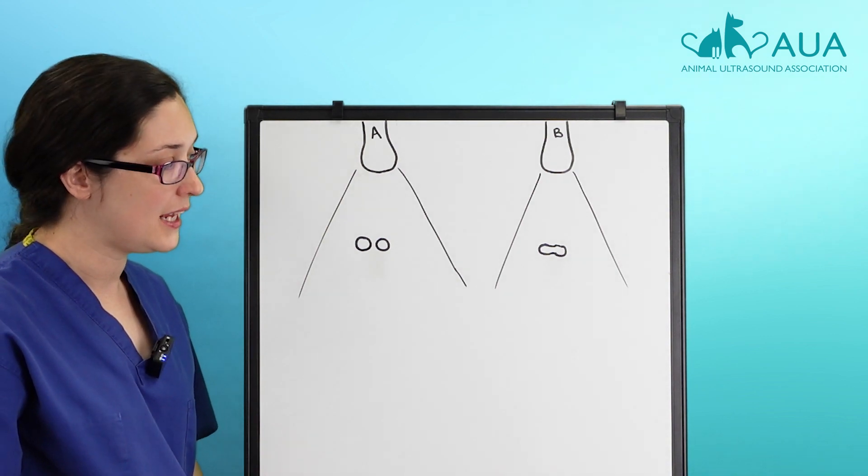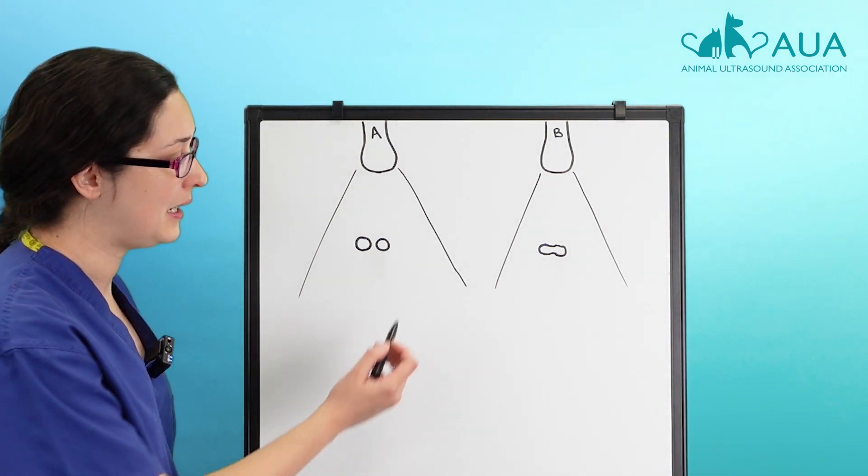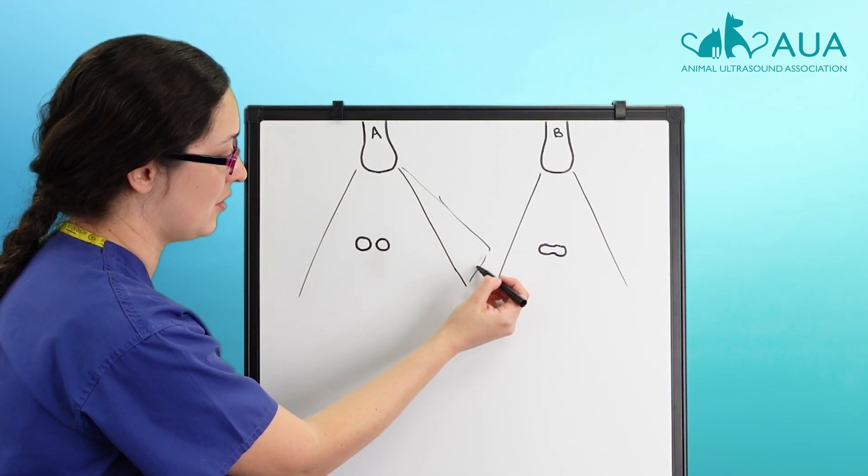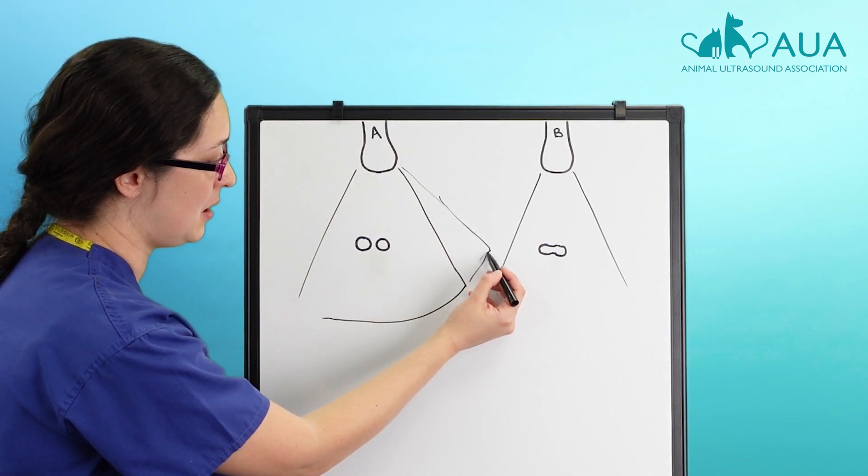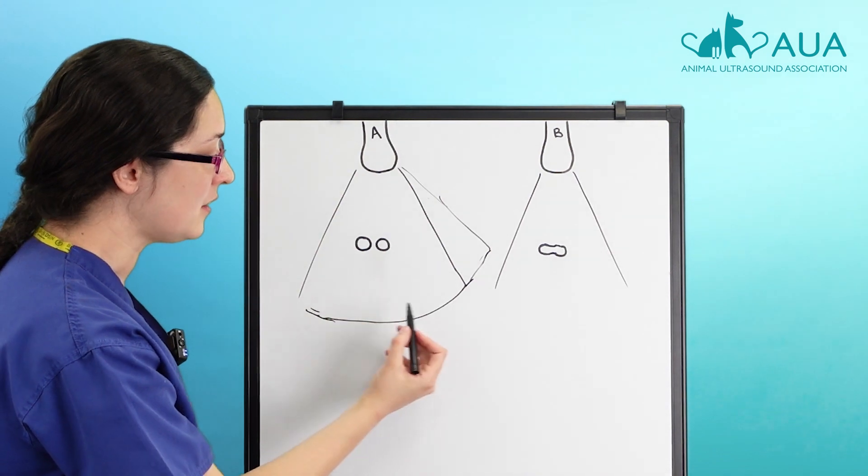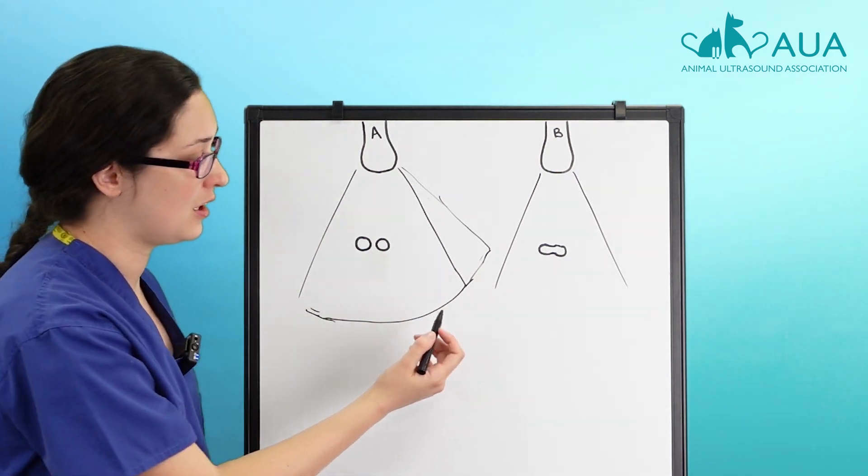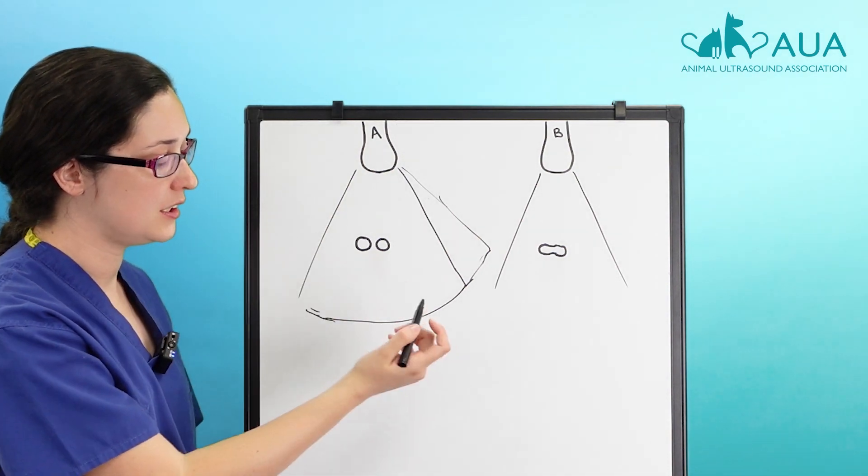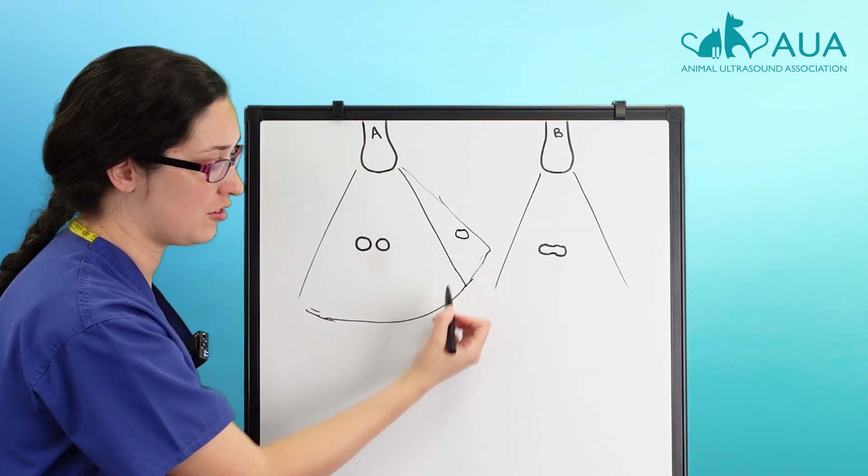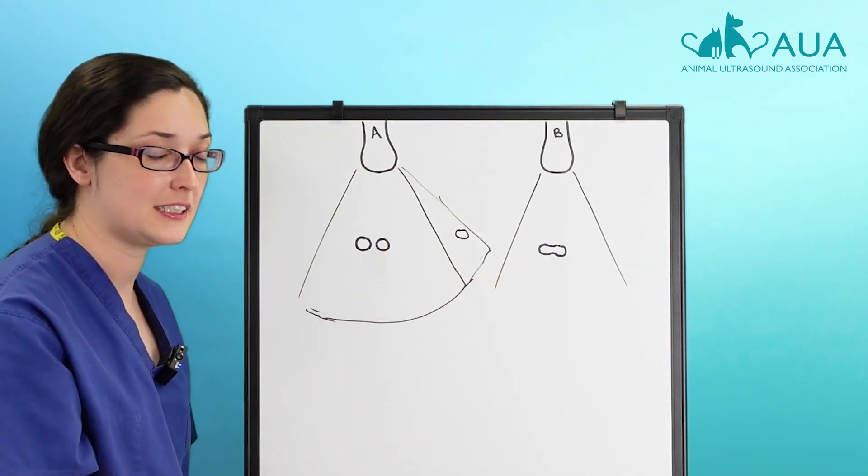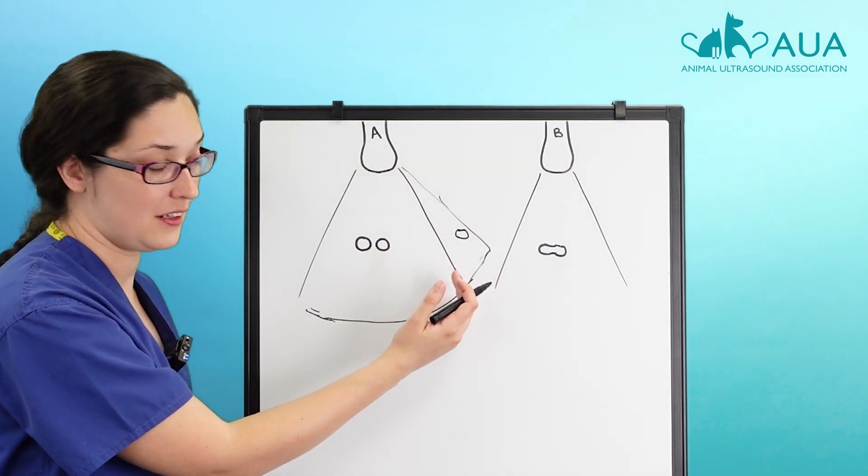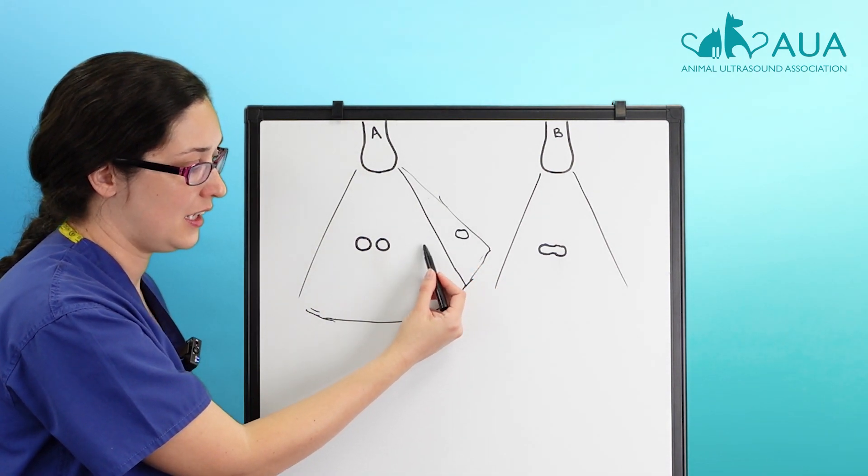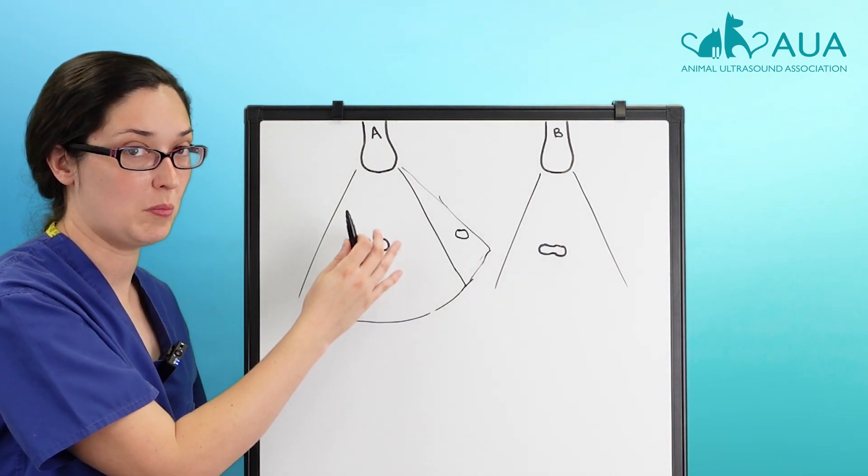There is also another plane that we don't see, a non-imaging plane, which is the elevation plane. So actually your beam is a kind of a 3D shape, something like this. And if an ultrasound machine has poor elevational plane resolution, then something that might be out of plane, another structure here, it's going to catch that and it won't understand that that's outside of where you're meant to image. And so it will place that in your imaging plane here, so on your monitor.